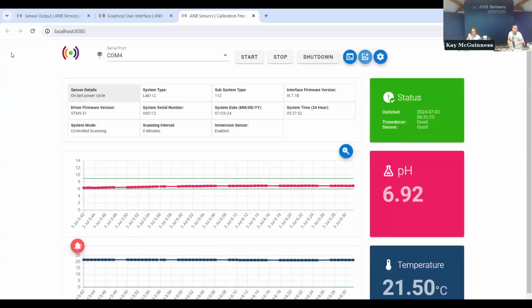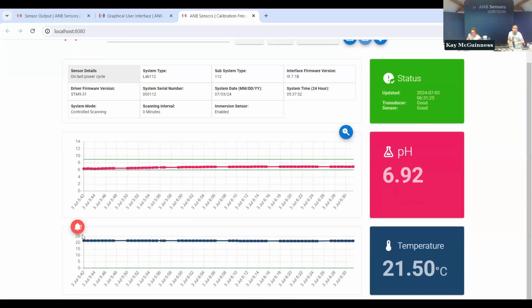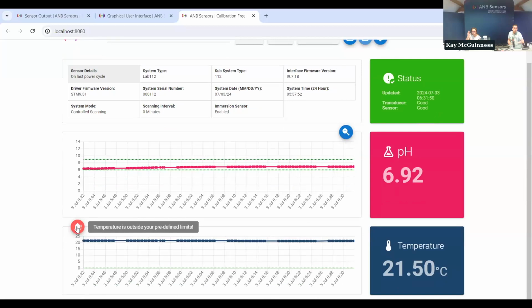For example, in pH we've set the limits from 6 to 9, and you can see these green lines are the limits that we've set. In temperature we didn't set any limits, so this is the error that you'll see - this is the kind of warning you'll see if your measurement is outside your limits.